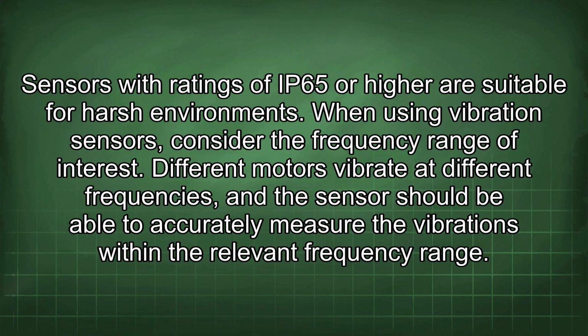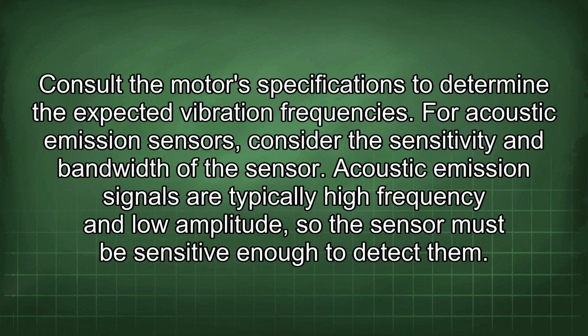When using vibration sensors, consider the frequency range of interest. Different motors vibrate at different frequencies, and the sensor should be able to accurately measure the vibrations within the relevant frequency range. Consult the motor's specifications to determine the expected vibration frequencies. For acoustic emission sensors, consider the sensitivity and bandwidth of the sensor.